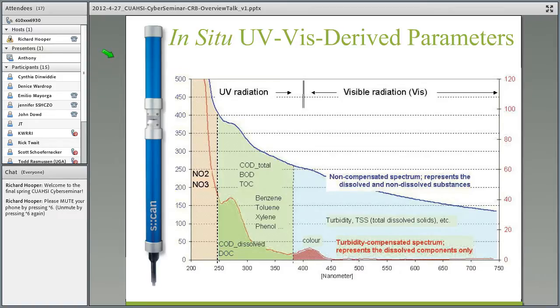We're playing around with some in situ submersible UV-vis spectrophotometers made by a company called s::can. They're from Europe. Satlantic makes the SUNA and the ISUS equipment. They were primarily designed for marine applications, but they're finding their way into rivers now that do similar things. Essentially, from this UV-vis, we can get the full spectrum, because it goes into the visible, you can get a turbidity, or actually because it's really full spectrum, you can calibrate it to something that more closely approximates total suspended solids. That's a typo, not by me, but by them.